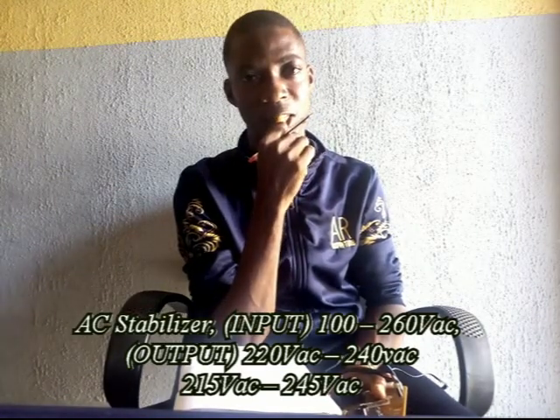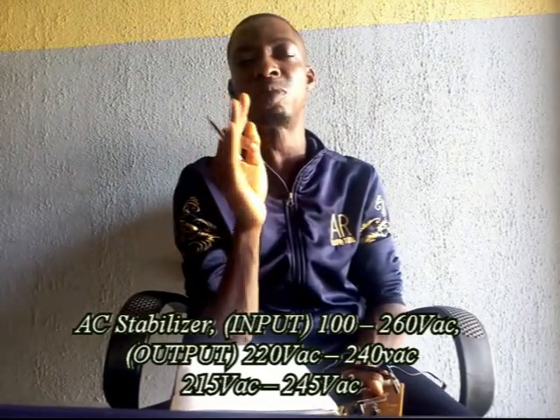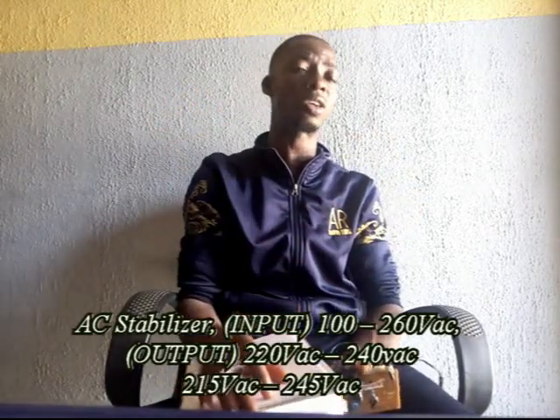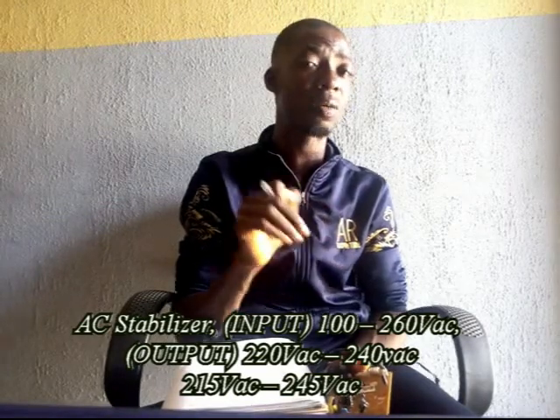Now let me go into stabilizers. What is a stabilizer? A stabilizer is simply an AC stabilizer that accepts voltage between the range of 100 to 260 volts and maintains it, giving you an output between 215 to 245 volts. That's a practical voltage — in write-up they will tell you 220 to 240, but practically when you are doing an adjustment, that's what it is.